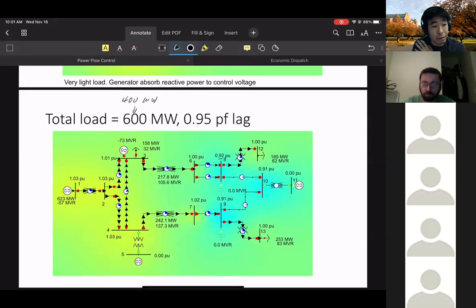Right, when do you press the big red button? So what is the desirable operating range that everybody knows for voltage? We have a guess. It's one per unit as normal operation, right? So the range we want to see is something like 0.95 to 1.05 per unit for voltage. Okay, so we want to see this. If you deviate a lot outside this range, then we start having problems.